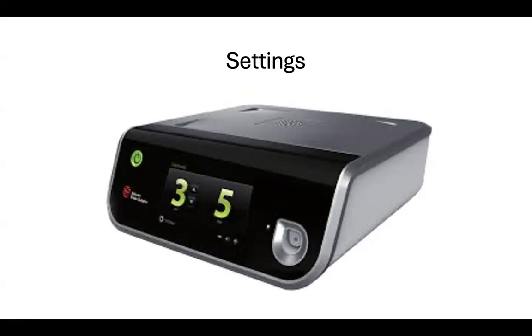And when it comes to the maximum setting, the frequency or the vibration is the same, but the length of vibration is going to be shorter. In summary, the amount of pressure you apply and the amount of time you spend on each tissue decides whether the tissue is going to get coagulated or cut. You can cut the tissue even at a minimum setting of 1, and you can purely coagulate the tissue even at a setting of 5, because it totally depends on how much pressure you apply and how long you do the process without injuring the tissue.